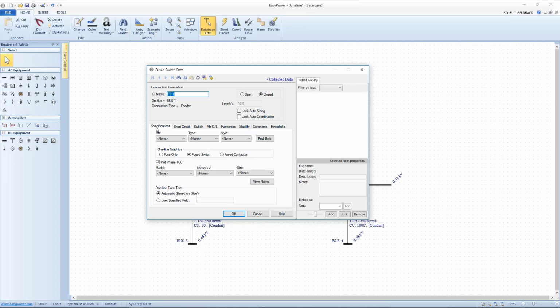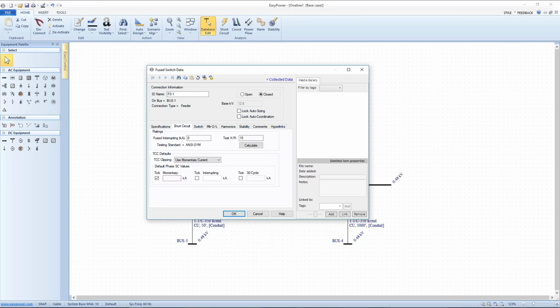He said, Jim, I've looked at the label on this fuse. It's an AB Chance fuse link, Model T. And now as I describe this, he said it's size 10. The tool finds it in the device library, and we're going to come here and make this a 0. And as I click calculate, it brings up a number, which means the tool has found the part number I've given it. It's been tested to an ANSI standard, and the X over R environment that the manufacturer used when it tested the fuse was 15.